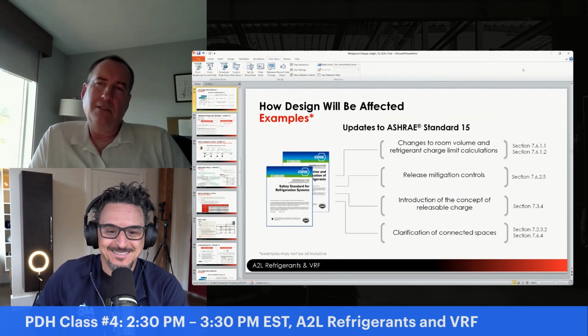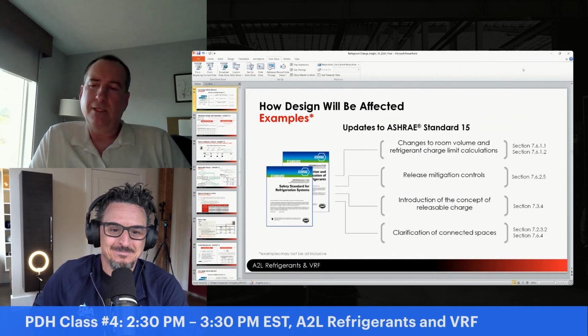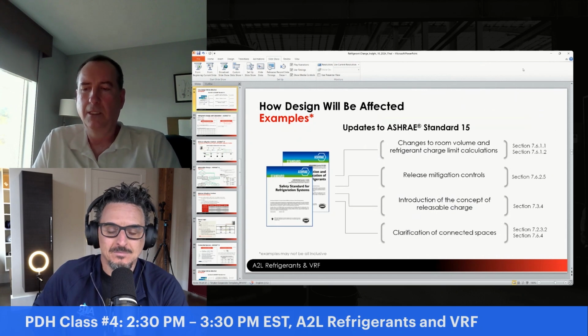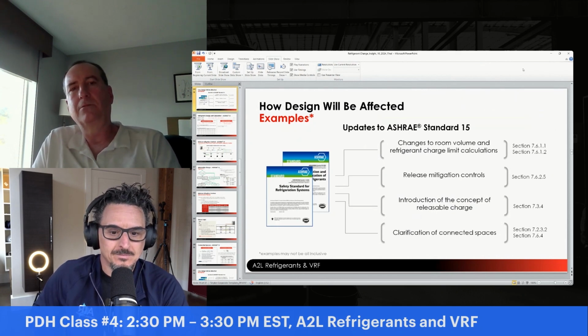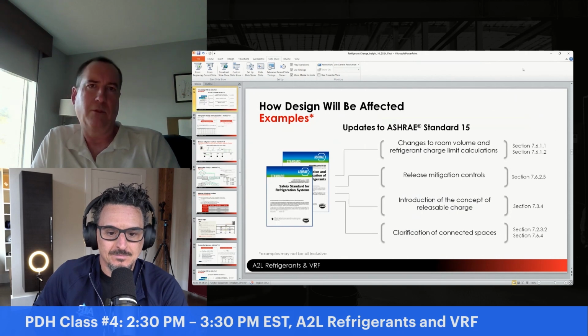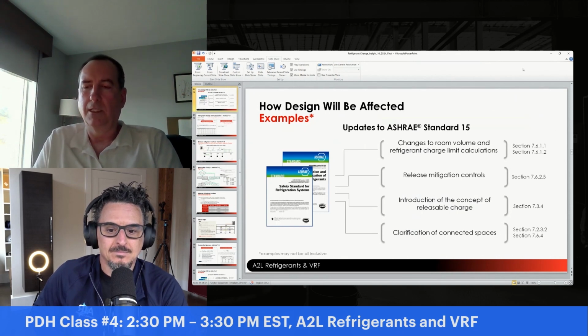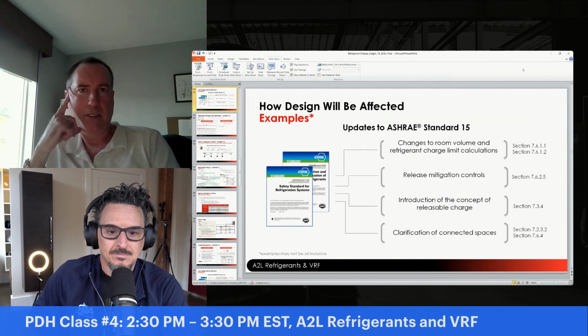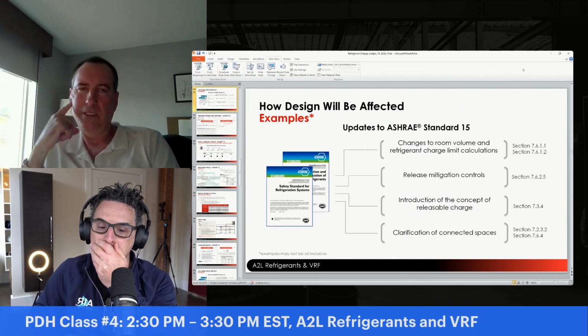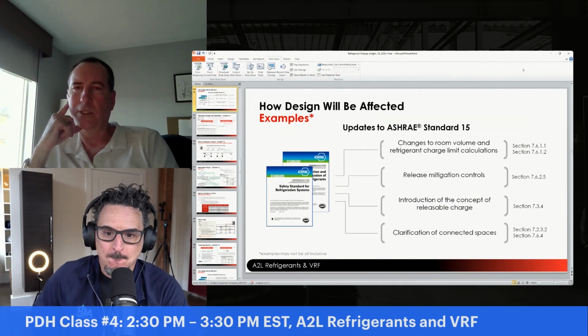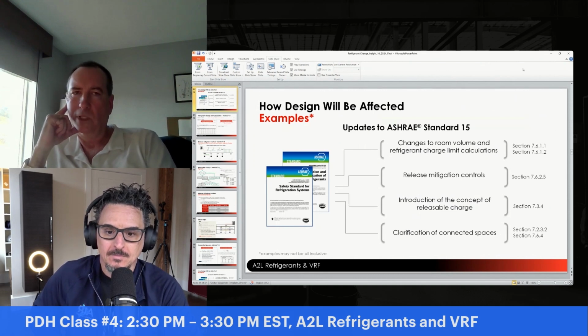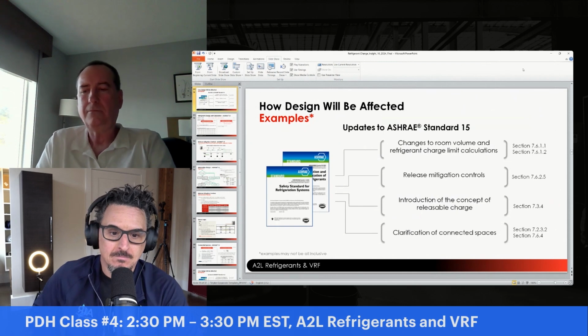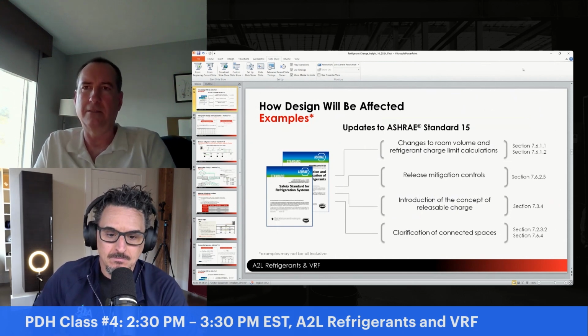So looking at how these designs are going to be affected, they did some updates to ASHRAE 15 and also to UL. They added new details and safety measures that enable the safe use of these new refrigerants. To remind everyone, ASHRAE Standard 15 is an application safety code standard, while UL 60335 is an equipment or product safety standard. Think about the tag on your hair dryer that says don't use this in the bathtub - that's an equipment product safety thing.